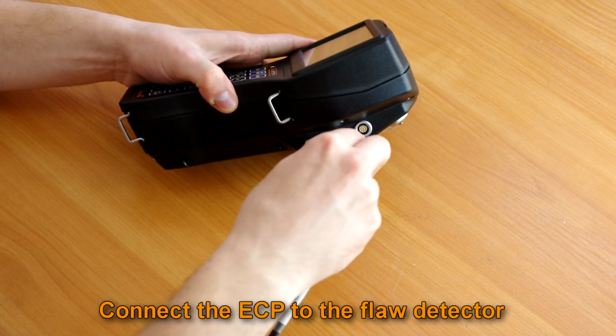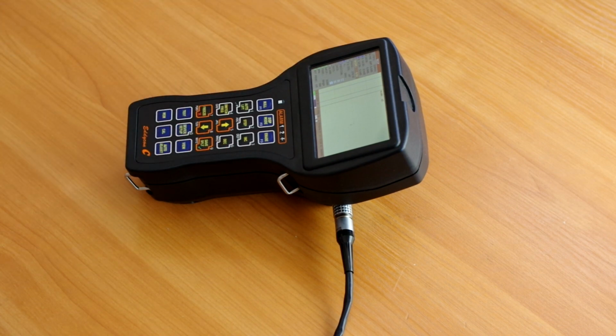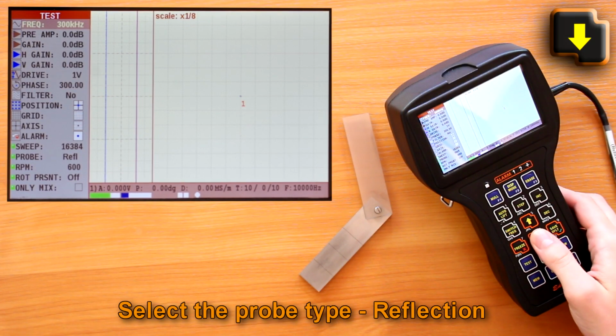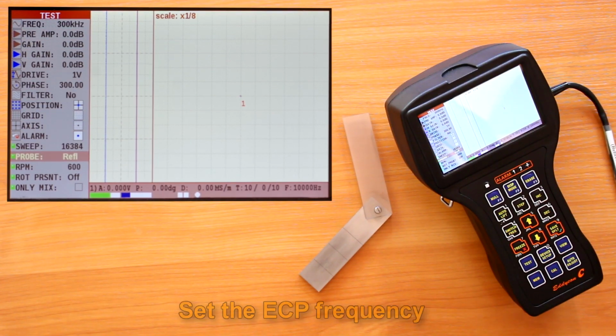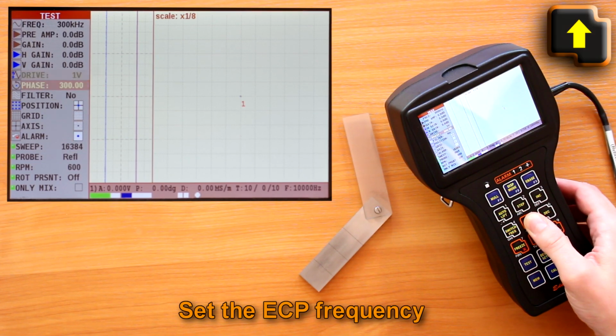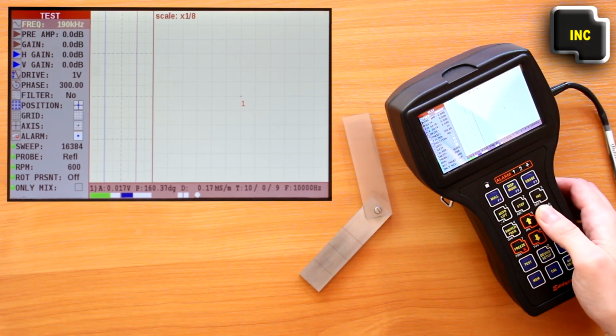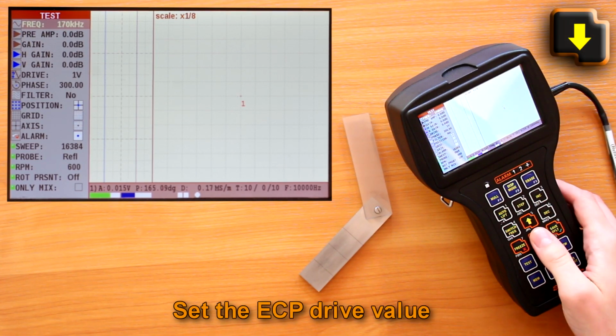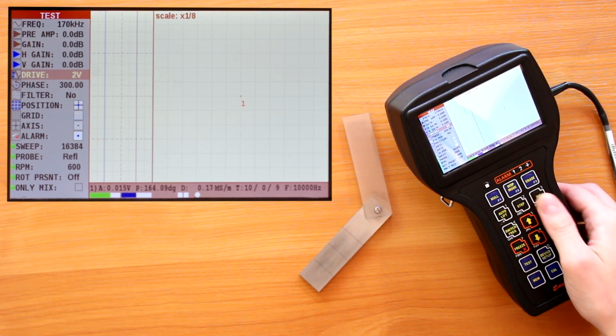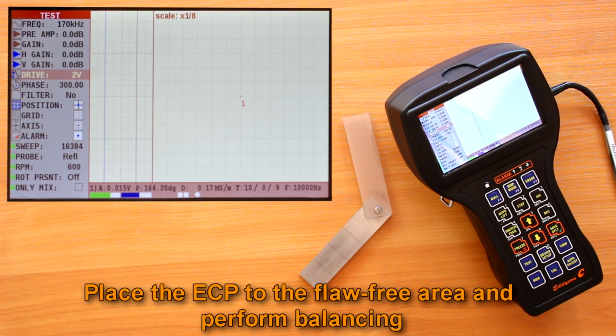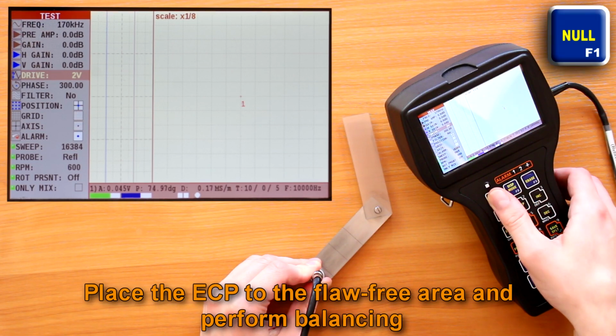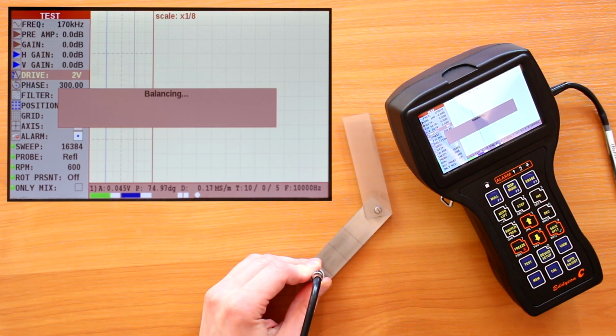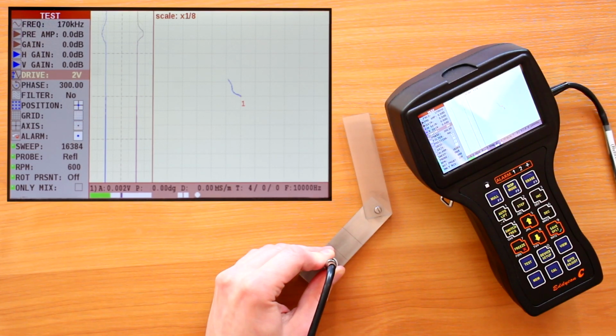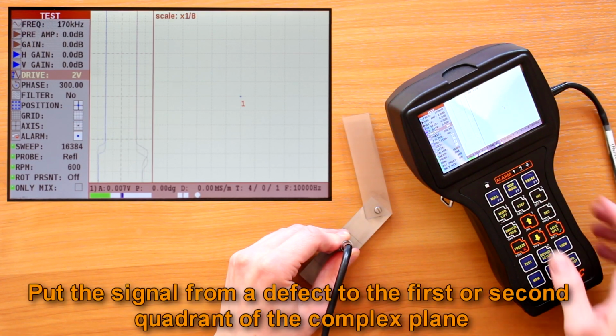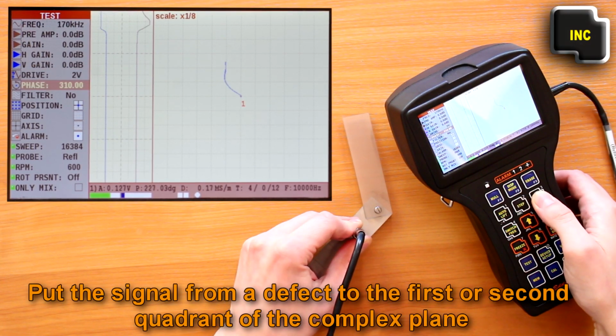Reflection probe. Connect the ECP to the flaw detector using a connecting cable. Select parameter probe in the test menu, reflection type. Set the ECP frequency in a range specified in the registration certificate of the ECP or on the probe marking. Set the ECP drive value according to its registration certificate. Place the ECP to the flaw-free area of a calibration block. Press the F1 key to balance the ECP. Put the signal from a defect to the first or second quadrant of the complex plane.